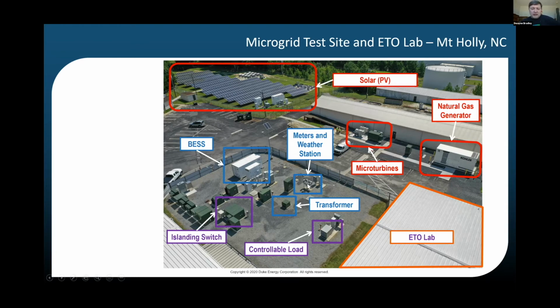We have a whole bank of meters. Traditionally we haven't really trusted a lot of the meter readings that come from these devices -- they can give us measurements of the amps, volts, and watts coming through, but we haven't trusted them to be highly accurate. So a lot of times we put in an extra high quality meter to measure the exact power output and input on those devices.